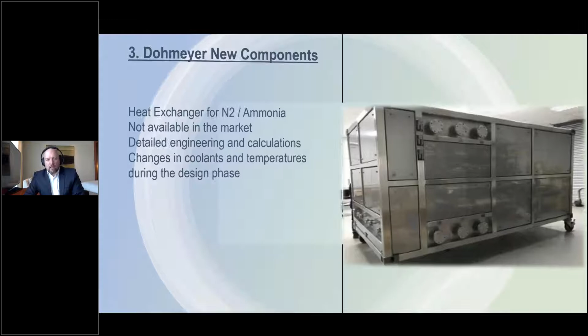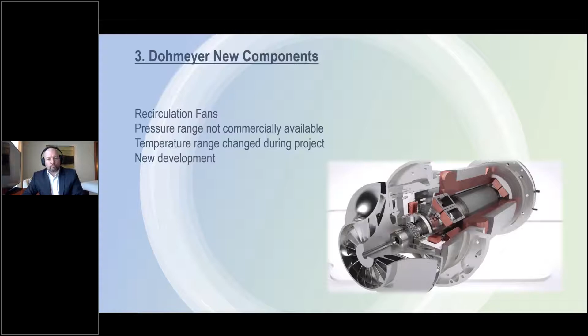At a certain moment in the project, we decided that we would recirculate the warm gases to reheat and regenerate the cold storage. As the P&ID was changing and the temperatures changed, we had to adapt our recirculation fans to a complete new temperature range that was commercially not available on the market. So we had to develop a complete new turbo compressor. This was another very big challenge for us to design and build.